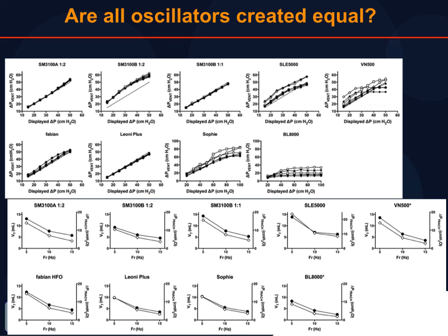Now, that's just a pressure thing. What really it's all about is the volume you're getting with the pressure. And what this translated to between the devices is that they all had different potentials to generate, at least in a test lung, different tidal volumes at different frequencies. So if you had a delta P of X and a frequency of X, it doesn't necessarily mean you always get the same tidal volume from each device. And you can turn this 2 ways. So we found that some of the devices at very, very high frequencies were only able to generate tidal volumes equivalent in our test lung of about 3 mils. So in a bigger baby, that may be a problem. In a smaller baby, that may not be a problem. Okay? And that was generally the German-speaking devices.